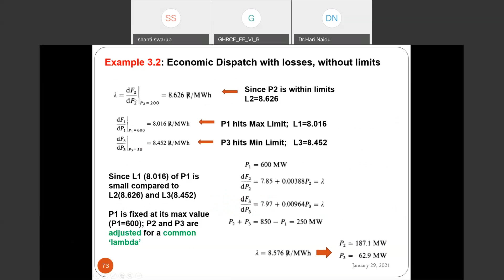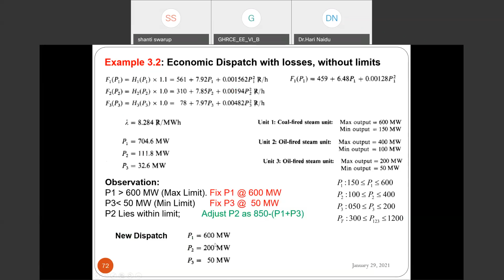Take for example lambda. Calculate lambda 2 - why? Because P2 lies between the limits, 100 to 400, so it's normal. Then I calculate lambda for this one, lambda comes as 8.626. P2 is within limits and lambda 2 equals this value. Then next I calculate for P1 and P3. Incremental fuel cost for P1 at 600 is 8.016. Incremental fuel cost for P3 at 50 is 8.4.